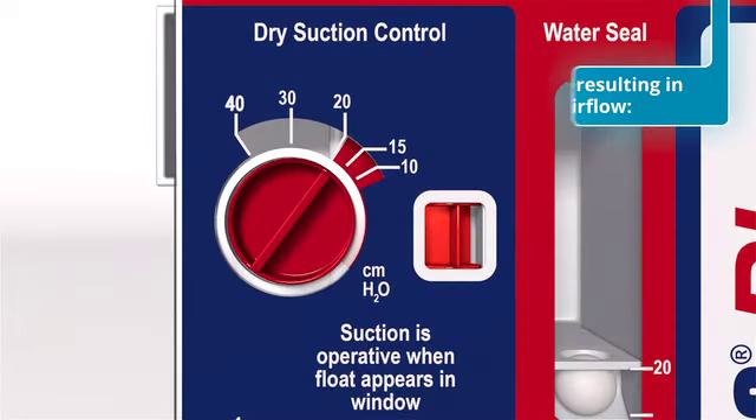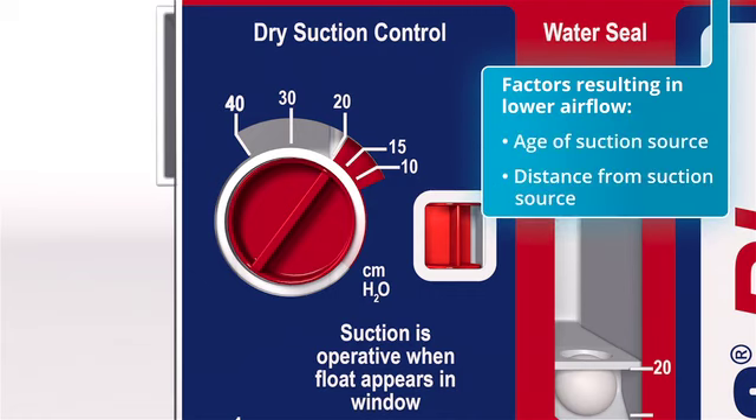Certain factors may result in lower source airflow, delivering lower-than-prescribed suction to the patient's Pleur-evac unit. These factors include, but are not limited to, the age of the suction source, distance from the source, and number of devices connected to the source. For this reason, and thanks to the regulator, suction can be turned up as high as necessary to offset low airflow and actuate the orange float, visually confirming adequate airflow has been achieved.